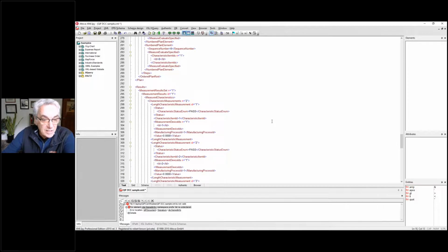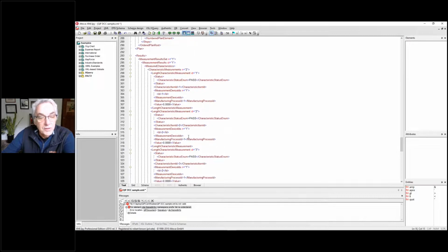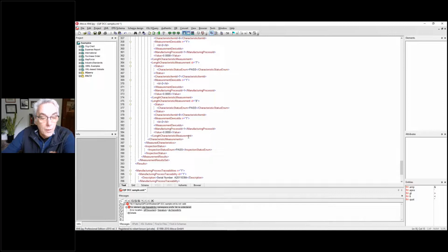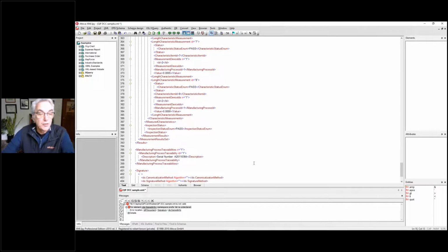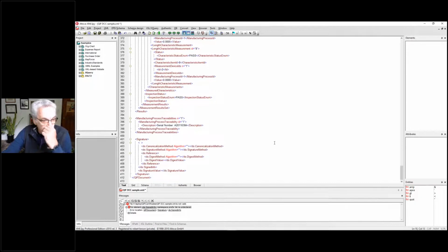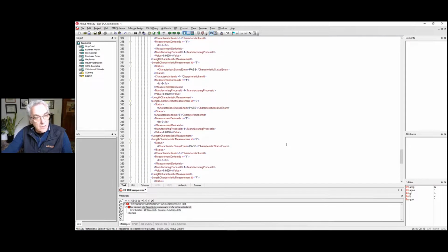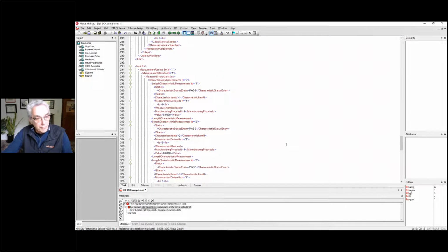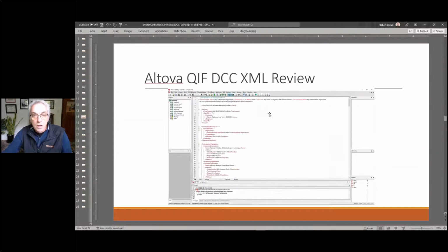So again, whether it's a pass-fail, which measurement device was used, what the value is, very straightforward. And we go through it, and then of course we've got manufacturing process traceability, so we can apply the serial number, and finally the signature. So as you can see in this sample, the Quality Information Framework, QIF, does support all the necessary elements needed for a digital calibration certificate.